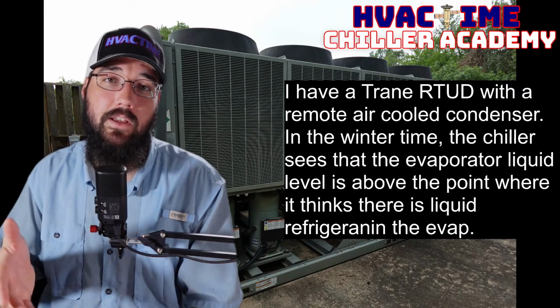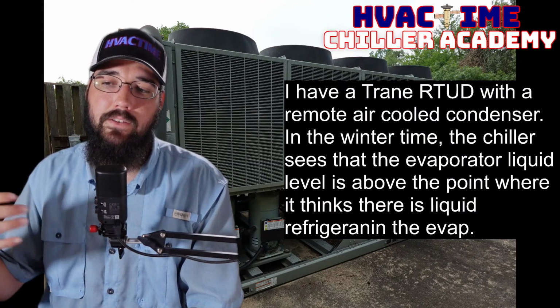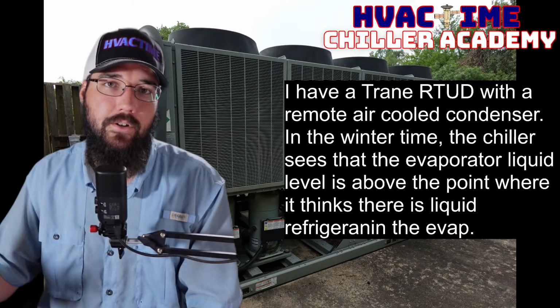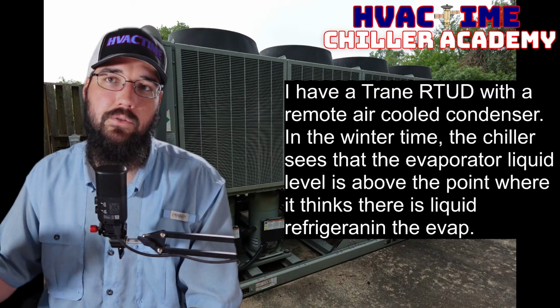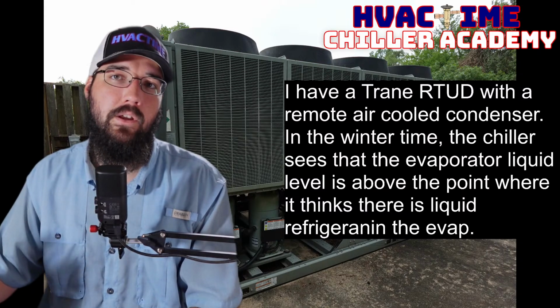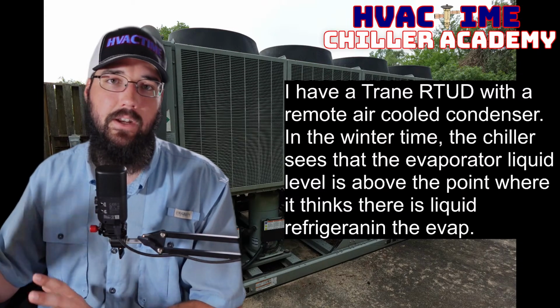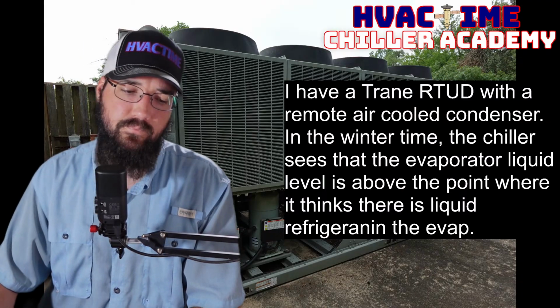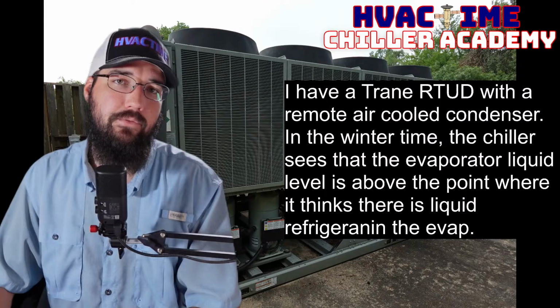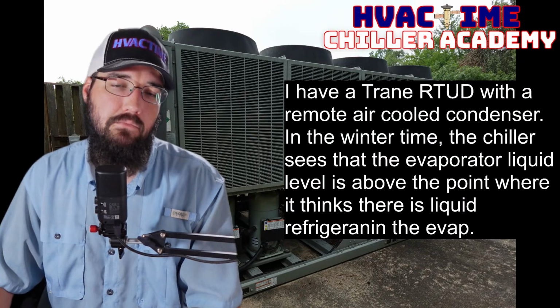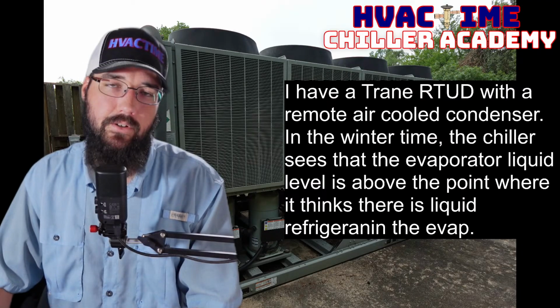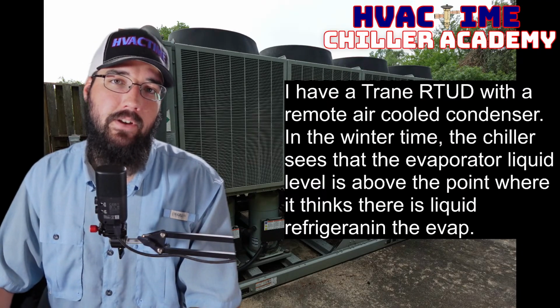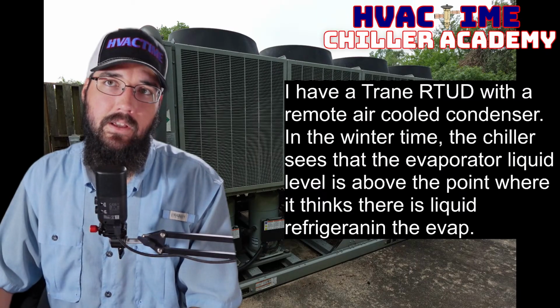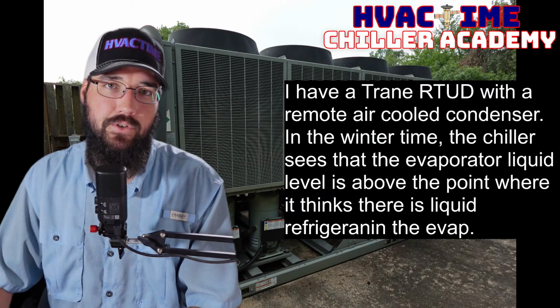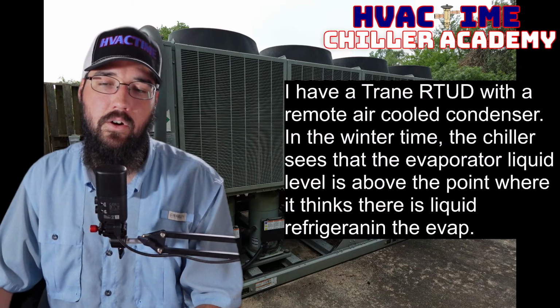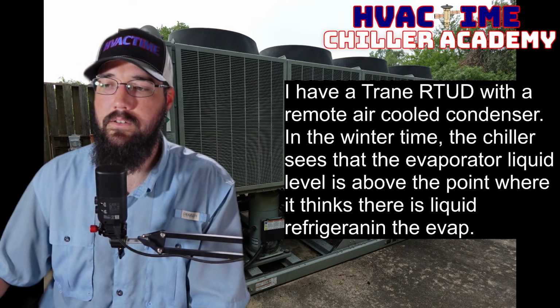And that could be a situational thing. That's the thing with remote condensers. That's a field installed aspect. That's no longer even an engineered part of the system. So we do have to do some additional field calibrating to account for whatever added line length and everything else that happens in addition to that. So it may be that other RTUDs may run at that lower saturation just fine, but it's possible that with your configuration, you may need a little bit of a higher saturation set point to still safely function. And that's where this conversation comes in, and our skill as a technician kicks in.